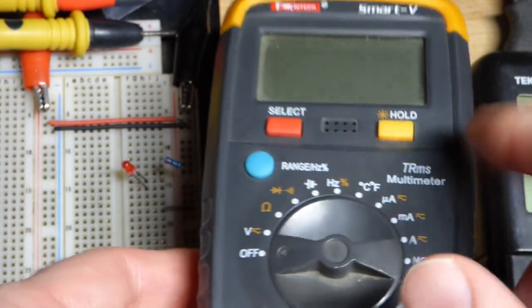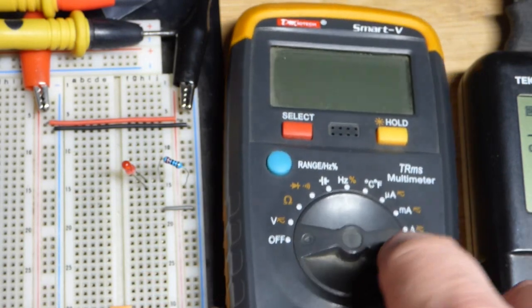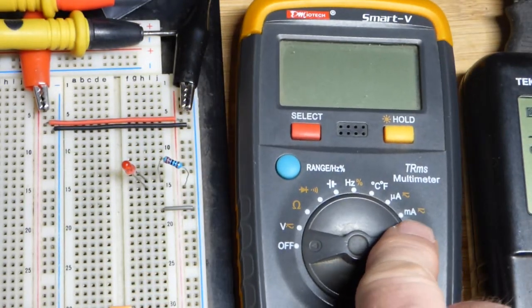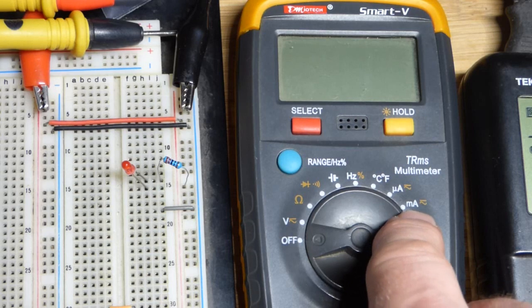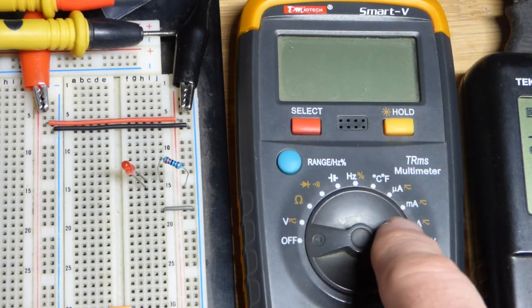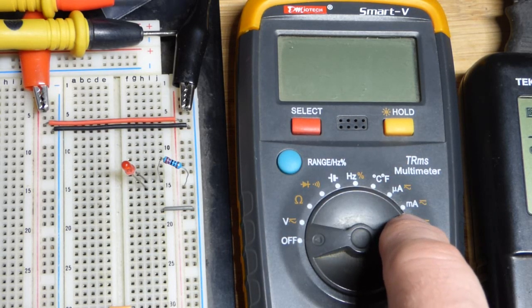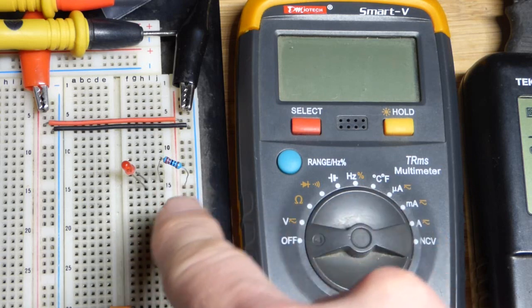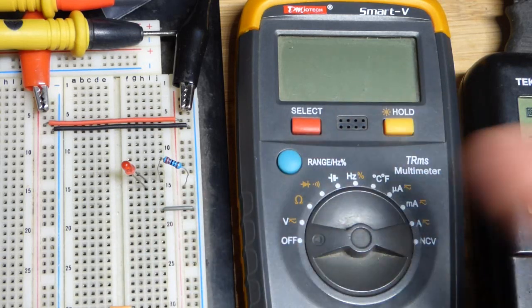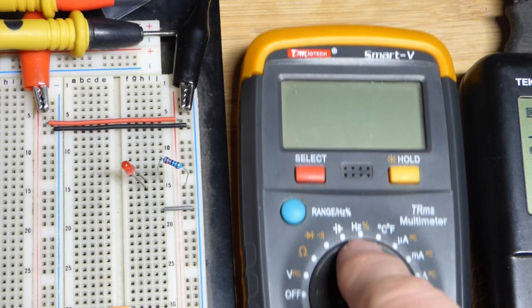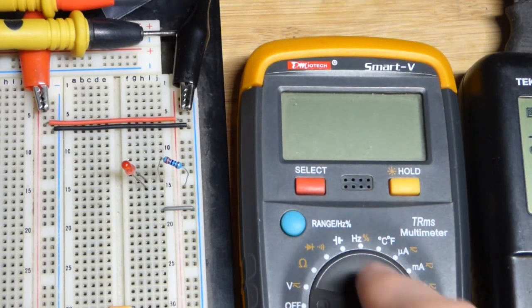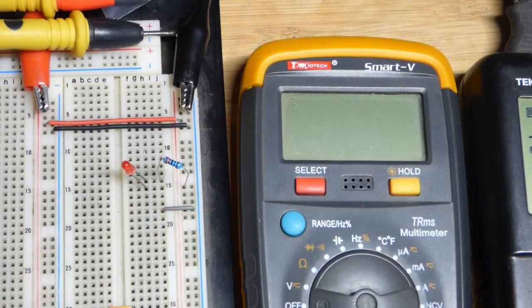Make sure you turn the multimeter off when you're done. First off, it keeps the battery lasting longer, and hopefully it has auto shut off. But also, you don't want to leave it in measuring current mode, because that's probably the easiest way to damage the meter, mostly by blowing a fuse. If you try to measure a voltage directly while in current mode, that's basically unlimited current, and so it blows the fuse to protect the meter. So avoid doing that.